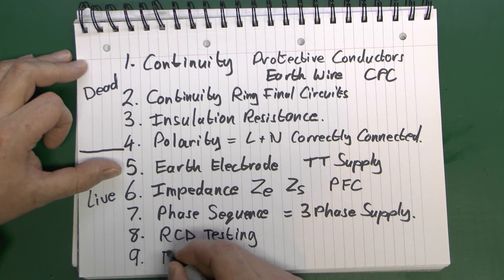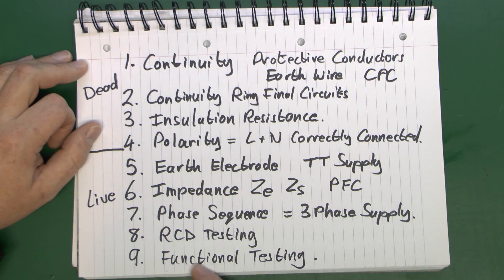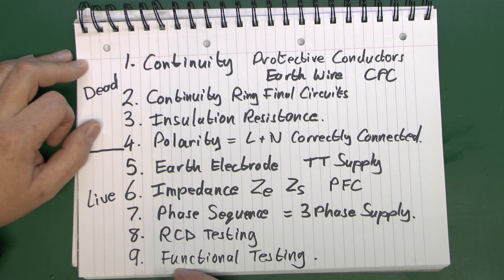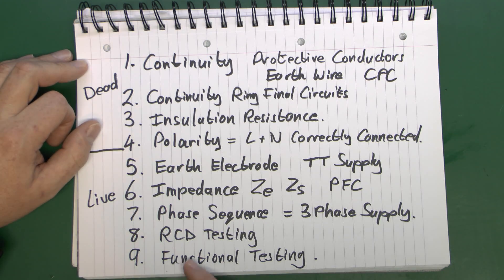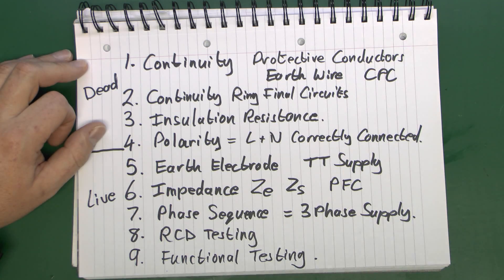And finally, number nine is functional testing. This basically means you're going to go around the building and make sure things like lights actually turn on and off from the switches controlling them. Any kind of fixed equipment — such as water heaters or storage heaters — make sure it does actually switch on and off and work as expected. It's worth testing at least one socket outlet per circuit to make sure it does actually power things as you'd expect. A handy way is just to plug in a kettle. You need to make sure all the equipment turns on and off as expected, because it's not unheard of for switches to be defective even if brand new — and it would be completely useless if occupiers moved into the building and found they couldn't turn the lights on.